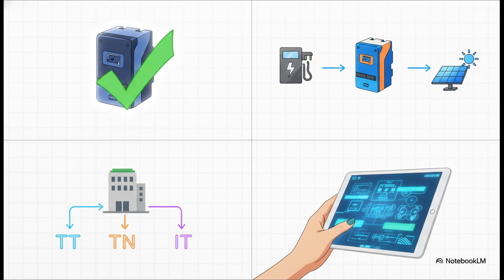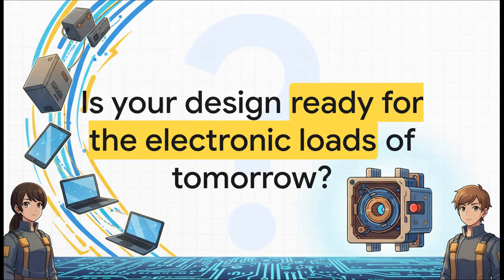You have to be thinking Type A, F, or B. Number 3, you simply cannot choose an RCD until you know the building's earthing system. It sets the entire game plan. And finally, number 4, if you are ever in doubt, the standards and the manufacturer's data are your ultimate source of truth. And that really leaves us with one final thought.